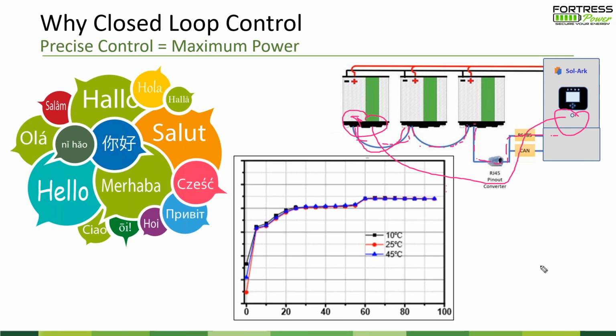So why is that necessary? Well, many inverters have state of charge controllers on their inverter systems, but historically that's because batteries have not had onboard computers in the battery system. So while we're all trying to calculate how full the battery is, it can result in communication error—even if we're speaking the same language, there's a gap in accuracy between what the inverter thinks the battery state of charge is and what it's actually at.